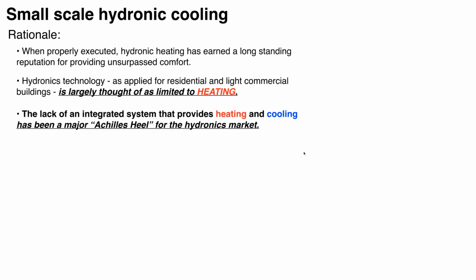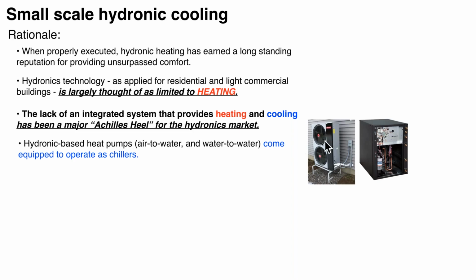And now with availability of hydronic heat pumps, and within that category, I've talked about water-to-water heat pumps that are typically tied to geothermal loops, or air-to-water heat pumps. And as you can see, air-to-water heat pumps is a rapidly evolving and growing sector of the market, and they'd be ideal. So whether we're looking at air-to-water here and water-to-water over here, today all these units come with reversing valves. So when you buy either of these heat pumps primarily for space heating applications, you're also buying a chiller at no extra cost. The reversing valve is built in. And obviously, you don't have to use it in the cooling mode, but the infrastructure within the refrigeration portion of the heat pump is there. It's just a matter of making some electrical contacts, and you'll switch the machine from heating to cooling.